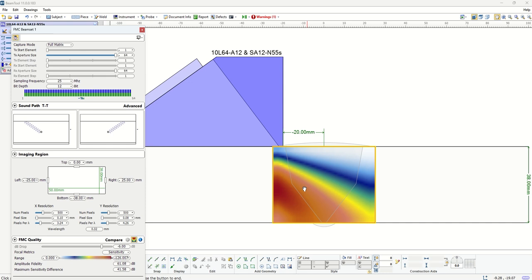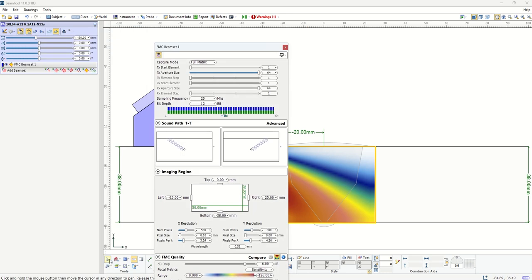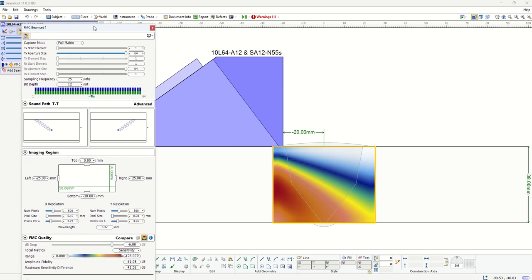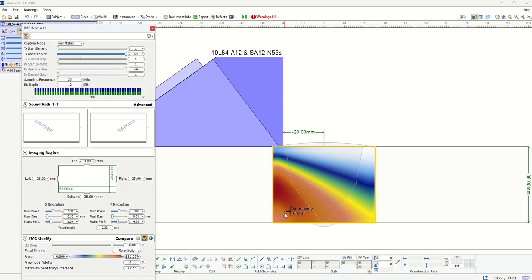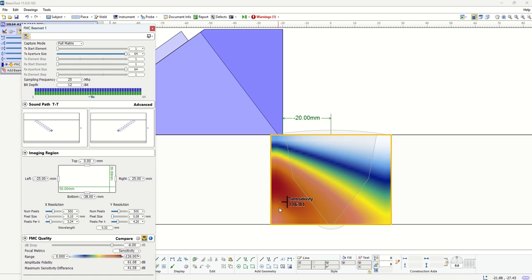What we know here, based on this, is that we have the highest sensitivity and larger values at the bottom left, and at the top right, which is the opposite side bevel, we have the lowest sensitivity, which is not a big issue because in many cases, like this case, we can have a two-side inspection. So we want to make sure that we are more sensitive to this side of the skew 90 that is close to the wedge. And here we see that along the bevels, unless we reach the very top that is very close to the surface, we have a very good uniform, high sensitivity.